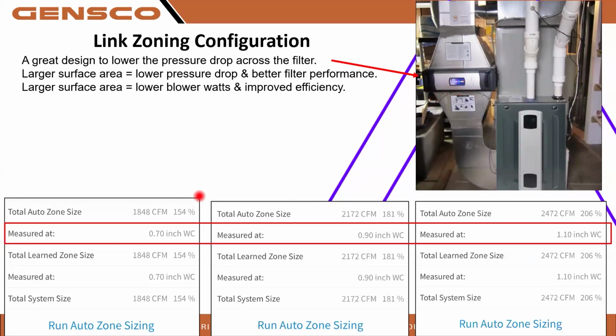This is through Link zoning, so this is a great illustration. We can actually dial in our static pressure on Link zoning, because we're using the blower motor static. At 0.7 inches, we're at 1848 CFM on this unit. At 0.9, we're actually producing more CFM, but the torque's going up. Then we can adjust it to 1.1 and look how much CFM, 2,472. So at the higher static, we're telling that blower motor to ramp up and use more wattage to produce more CFM.